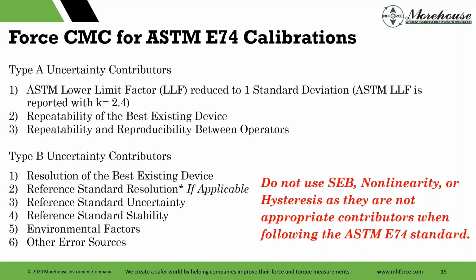Though the reason this slide is here is because my cal was done in accordance with E74, and if you look at it, there's not much on the spec sheet besides probably environmental factors. I would take side load sensitivity and some other things, but what people end up doing is they throw in this SEB, nonlinearity or hysteresis instead. So the way the E74 standard works is you assign coefficients, polynomial equation with coefficients that tell you that, hey, when I apply this force, my instrument should read this, and it does that curve fit for you, and therefore negates the need for nonlinearity of that system.